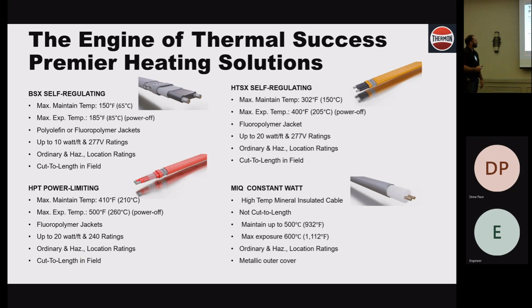To go back to our self-regulating cable, this is our low temperature polyolefin based self-regulating cable. You saw the curve yesterday on what self-regulating does - it essentially cuts itself off as it heats up. The main thing is you don't want to use it if your tube temperature is going to get anywhere above 185F, you're going to damage the cable. It's polyolefin based, so it's going to melt and won't work. But if it is going to get above those temperatures, we have other options.